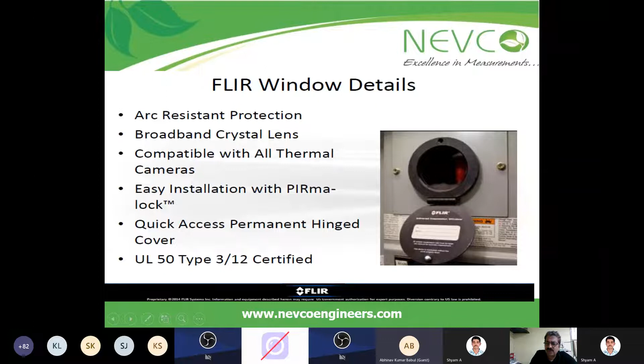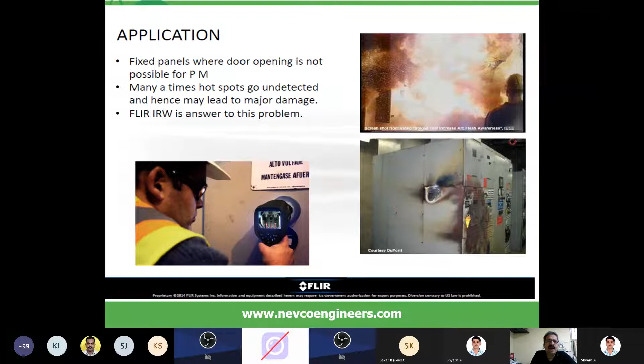For fixed panels where door opening is not possible for preventive maintenance, you have to use these windows. This window has been given so that through the hole you can find out the temperature if any part is heating up. Many times hot spots go undetected, and hence it may lead to major damage.